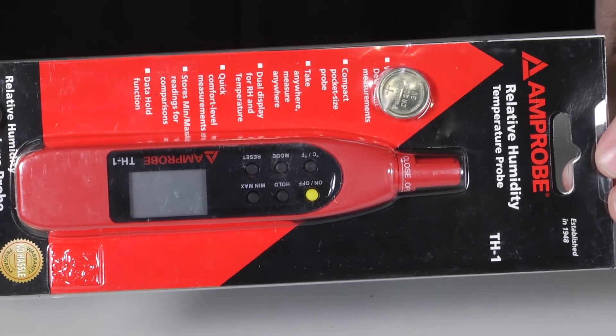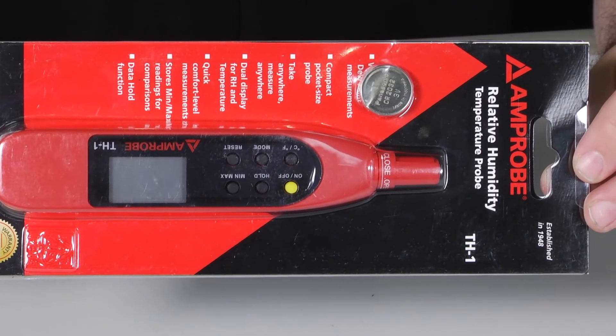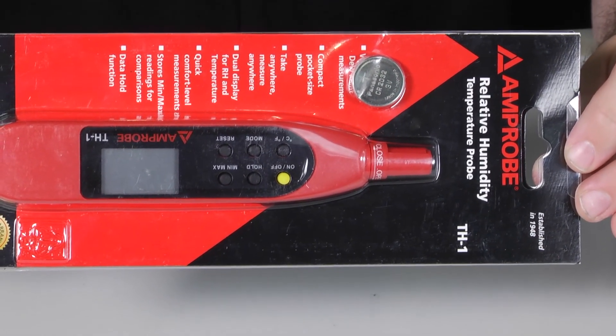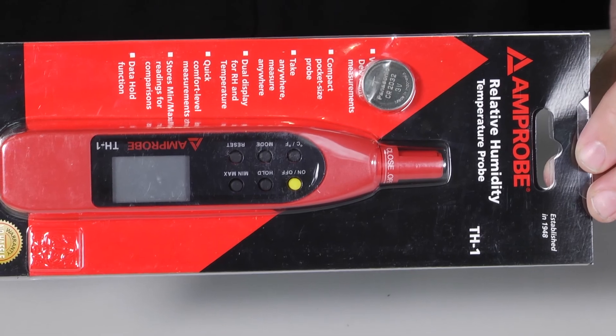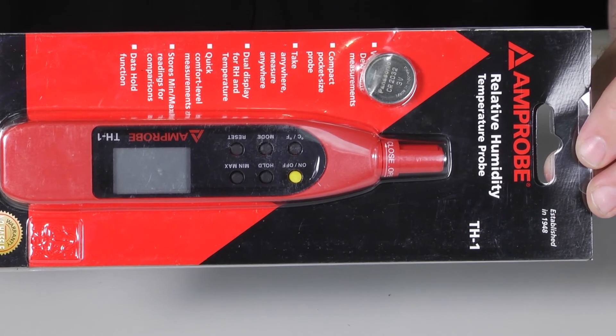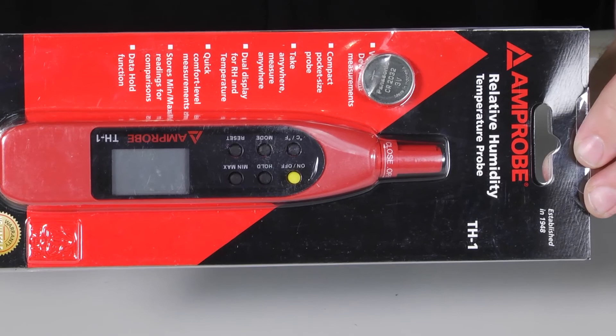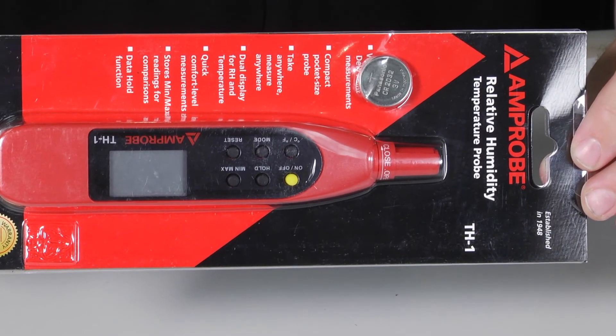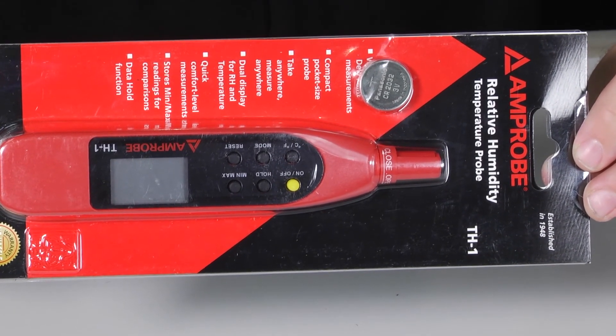And look, we've talked about the value of having a psychrometer before, but if you want to know how to charge a system that's got a fixed metering device, you've got to have a psychrometer for indoor wet bulb temperature. If you want to calculate total heat of a condensing unit or the air conditioner of what it's absorbing, you can take the wet bulb numbers and convert them to enthalpy.